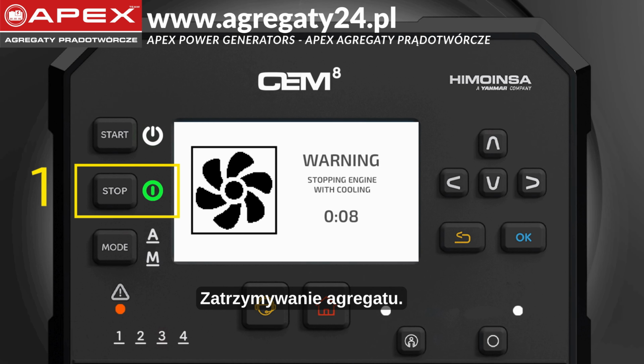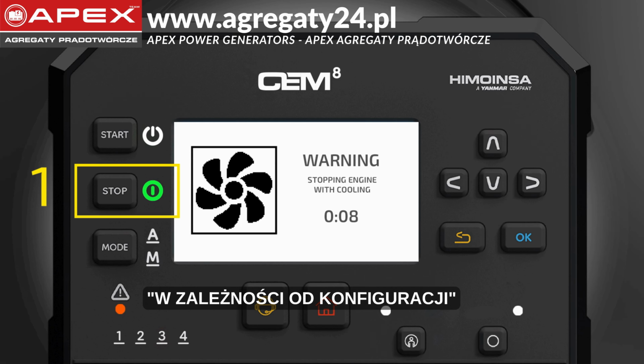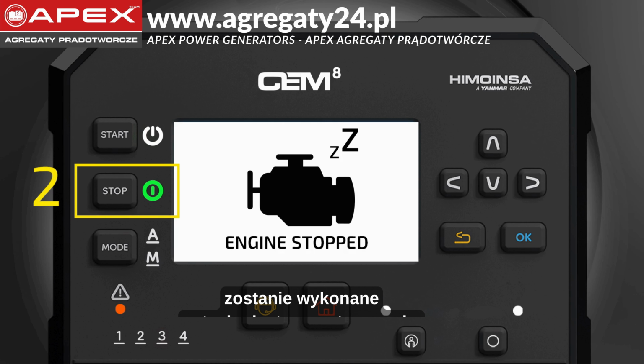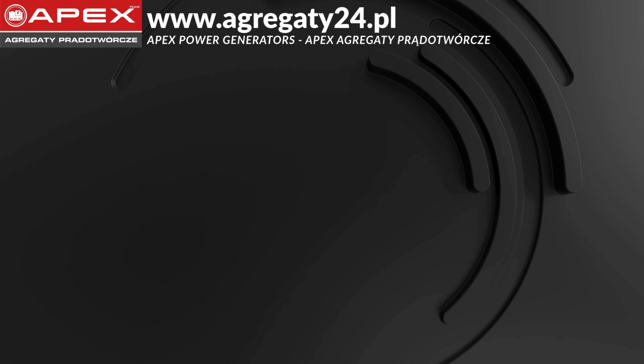Stopping the generator. To stop the generator, press stop once to perform a cool-down stop. The engine will shut down and the radiator will keep running to dissipate heat. If you press stop a second time, an immediate stop will be performed. The stop button only works when the generator is in manual mode.